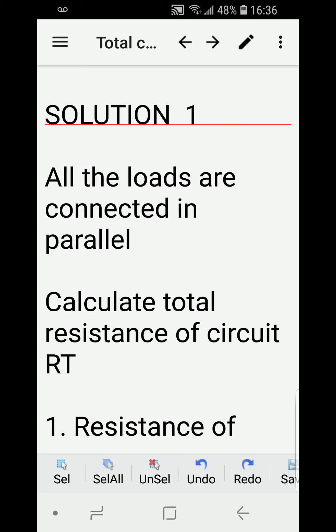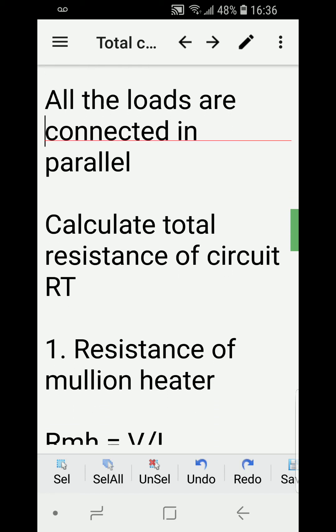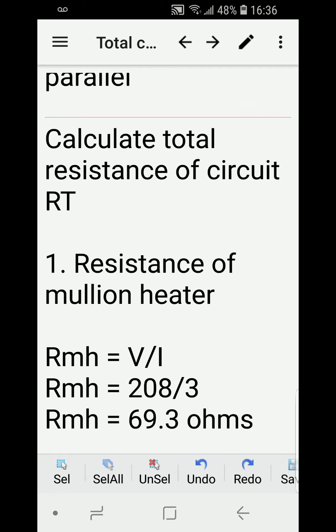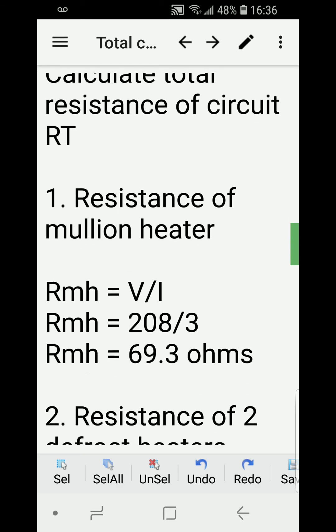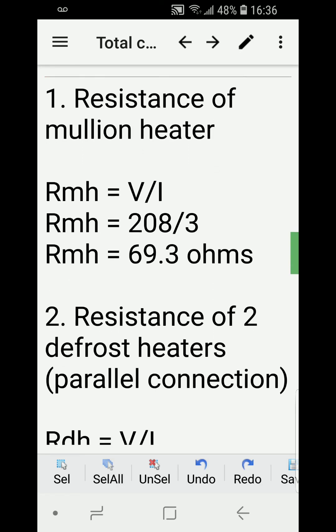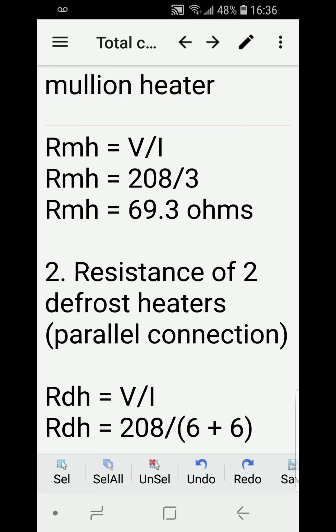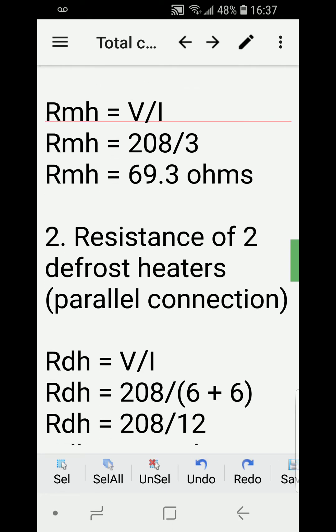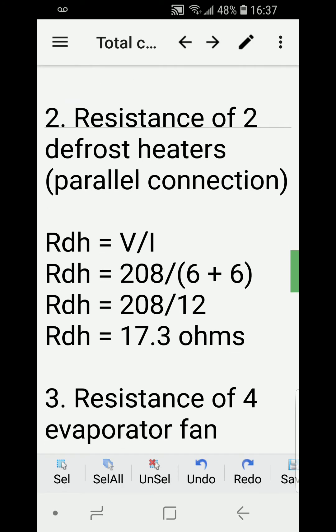I have two solutions. The first is solving for the total resistance first, and the second is just adding the individual currents. All loads are connected in parallel, so we calculate the total resistance RT. First, we calculate the resistance of the mullion heater: R_MH equals voltage over amperes, which is 208 divided by 3, giving us 69.3 ohms.